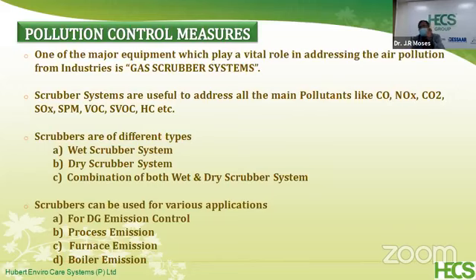Thereby, you make at least 70% of the dust reduced. That is, if our DG is giving 100 units of dust, it has to be brought down to 30. We can achieve that with wet scrubbing and dry scrubbing also. Over the last 20 years, in big IT parks and many other companies, we have put these scrubbers in the DG sets, especially where the population is more within the city. ITC Chola Sheraton, for instance, has a separate DG scrubbing device, and so do most IT parks in Chennai.